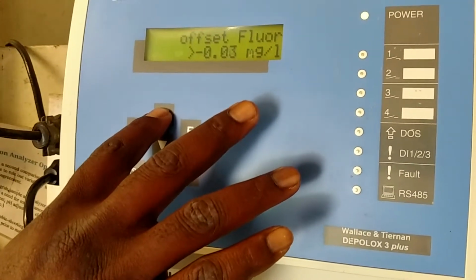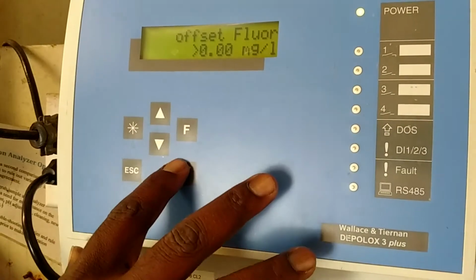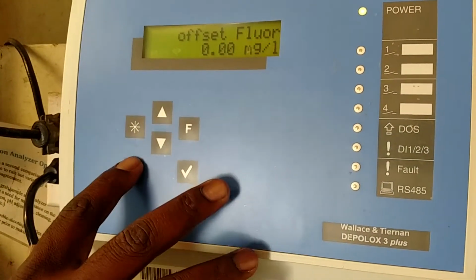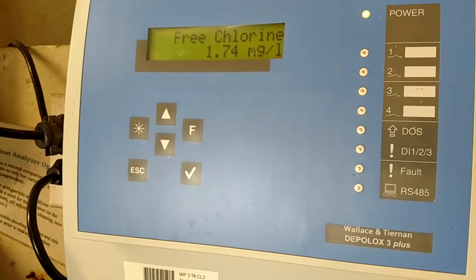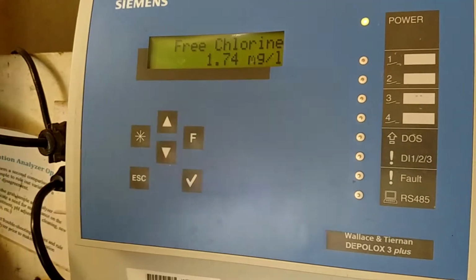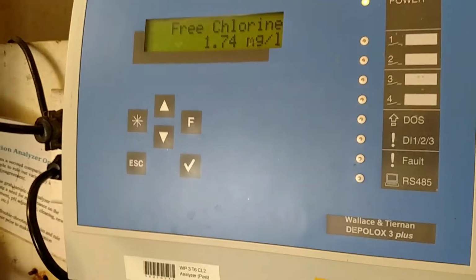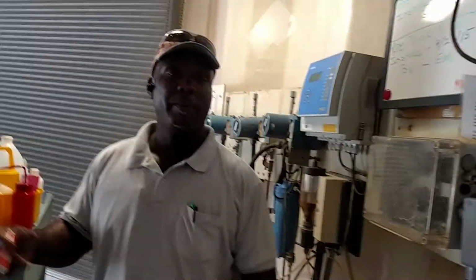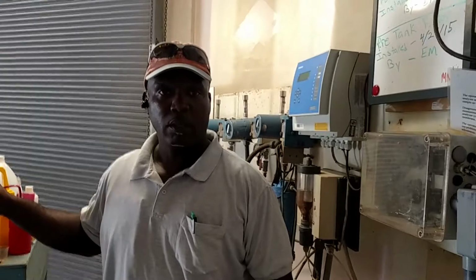So whenever I see that, every now and then I'll glance and see what they're actually reading, and just hit the escape twice to get back. But I'll look and see what they've been reading out, and I'll look at the analyzer. And if the analyzer is way off, I just go ahead and enter offset. And normally I make that notation on my calibration sheet, monthly calibration sheet. So that way it's always a reminder to go back.